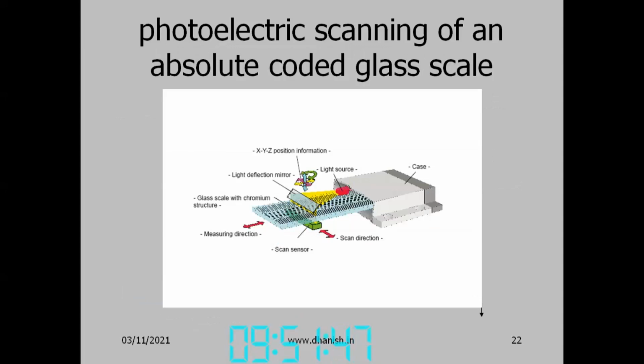So how the glass scale works is shown in more detail here. Light source, light is reflected by the light deflection mirror and falls onto the scale. On the other side, we have a scan sensor, and the scan direction, measuring direction. As it moves along the measuring direction, the number of lines crossed. So glass scale with chromium structure. There are lines on the scale, and the number of lines traversed is counted, and we can get the displacement of the scale.